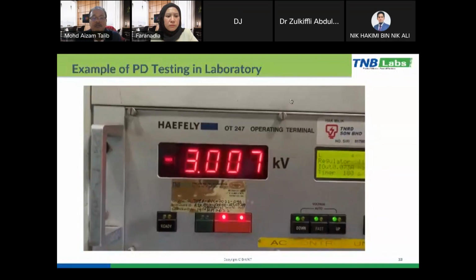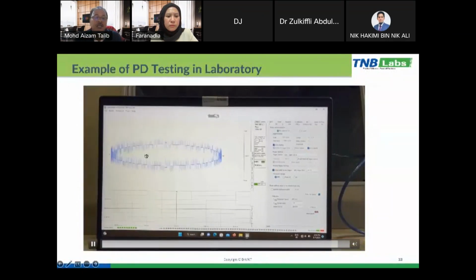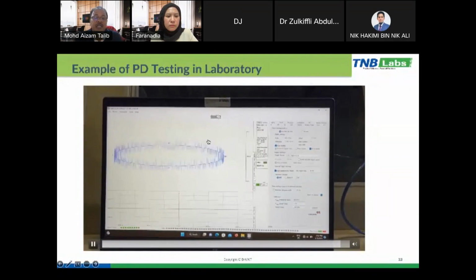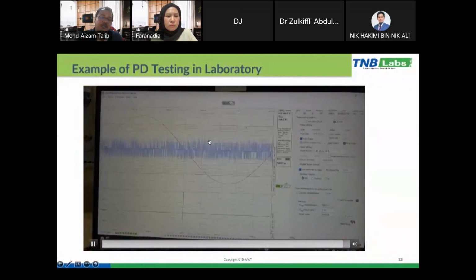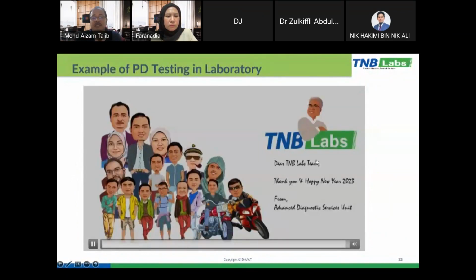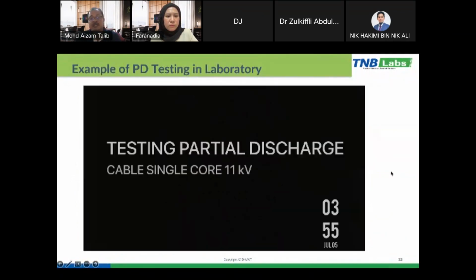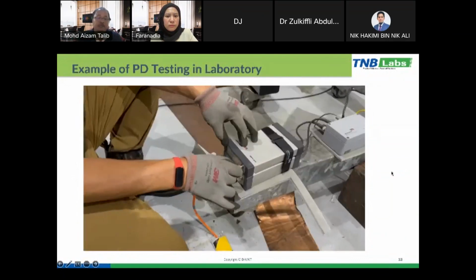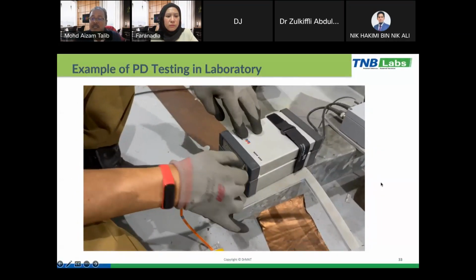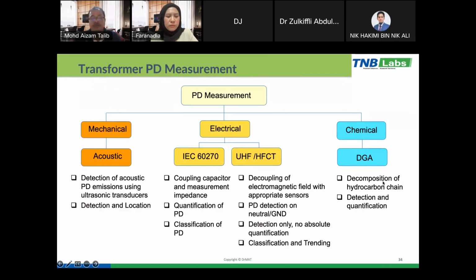Slowly we increase the voltage, and then we measure the PD through the ellipse signal. We can transform also to the phase-resolved PD patterns. So okay, that is the video of how this PD testing was conducted in the laboratory for the 11 kV single core cable.